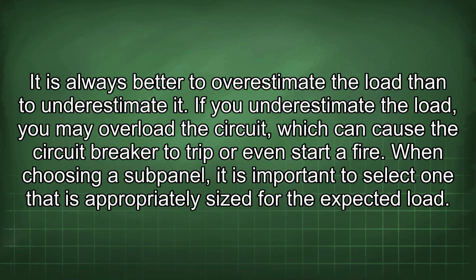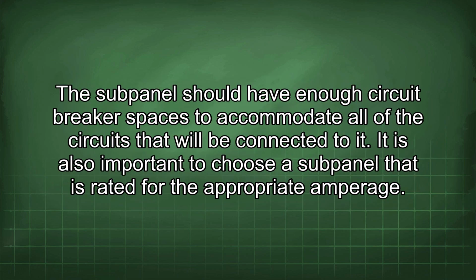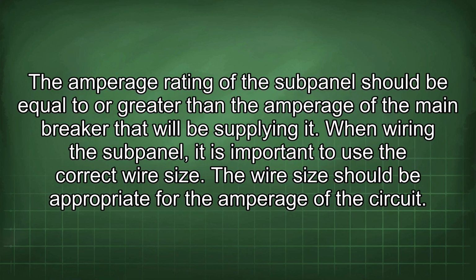If you underestimate the load, you may overload the circuit, which can cause the circuit breaker to trip or even start a fire. When choosing a subpanel, it is important to select one that is appropriately sized for the expected load. The subpanel should have enough circuit breaker spaces to accommodate all of the circuits that will be connected to it. It is also important to choose a subpanel that is rated for the appropriate amperage. The amperage rating of the subpanel should be equal to or greater than the amperage of the main breaker that will be supplying it. When wiring the subpanel, it is important to use the correct wire size.